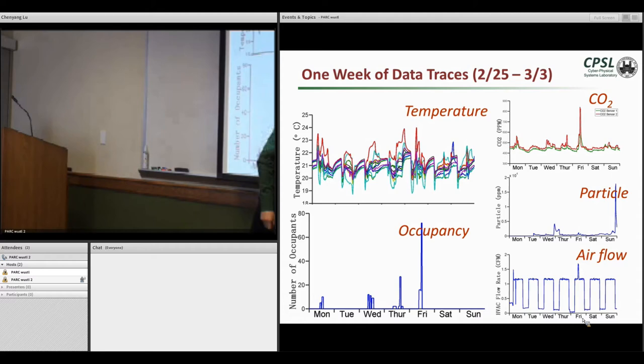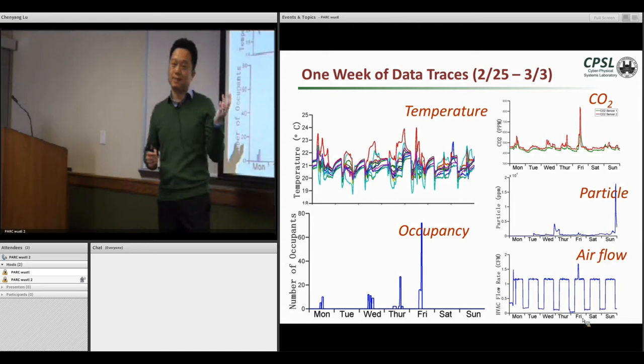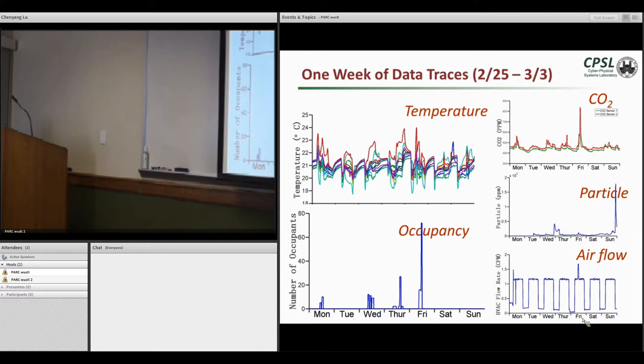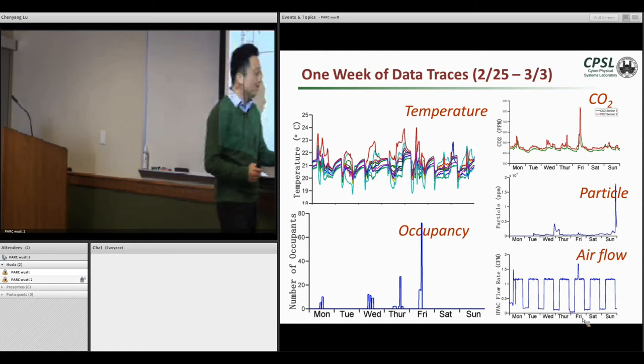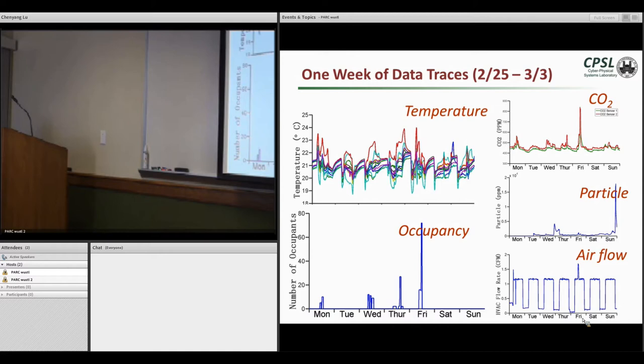But the problem is you can see it operates on pretty regular intervals. Right now, even though this is about the best HVAC system you can get—an industrial-grade system—it essentially operates on a fixed schedule. It turns on at 6 a.m. every day and turns off at 9 p.m. every day, operating at a pretty constant airflow rate. Occasionally, when there's a big crowd, like 80 people in the auditorium, you see it trying harder to do more ventilation into the space.